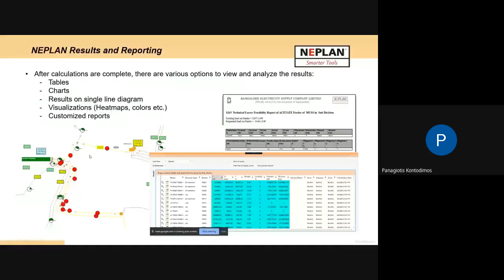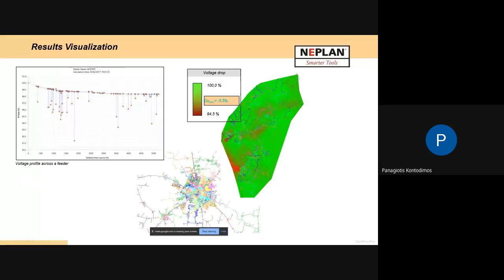We also have other possibilities, like heat maps, where we can see immediately in the network where there's a problem. By looking at the heat map, I can see immediately where low voltage areas are in the network. I can see across the feeder how the voltage profile looks, and if I add, for example, a shunt capacitor, how this profile can be improved.